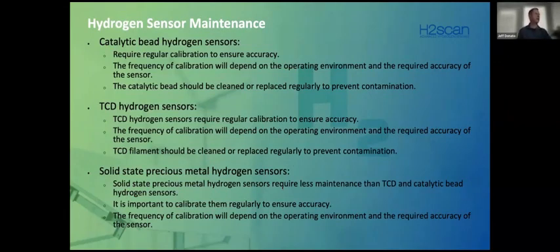So you have catalytic bead sensors, which are kind of the traditional type of sensors that are out on the market. But just keep in mind that some of the concerns that we have at IEEE about the use of sensors is that the user, the person who's required to maintain these units, understands what the maintenance requirements are. Some of these sensors, for instance the catalytic bead sensors, require calibration every 3 to 6 months. And so we do see a lot of sensors going into various applications and not maintained. That can give you a big false sense of security because they will drift.